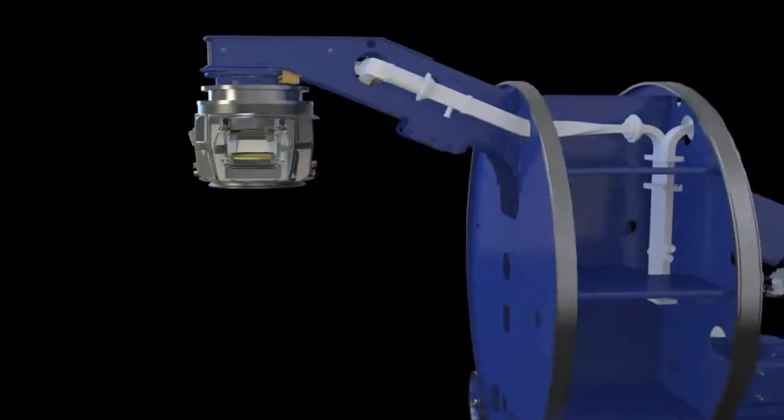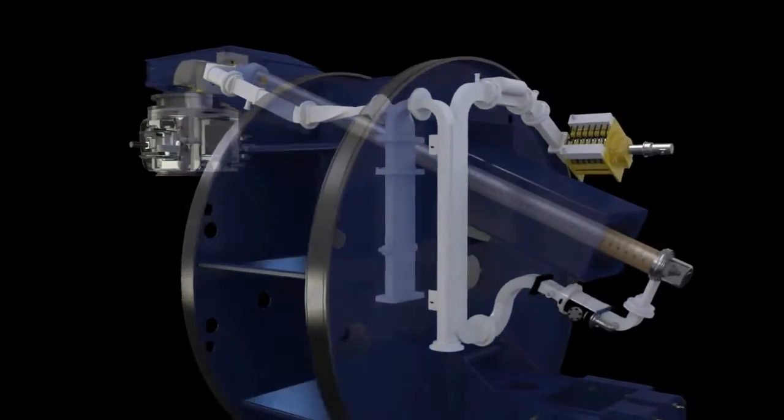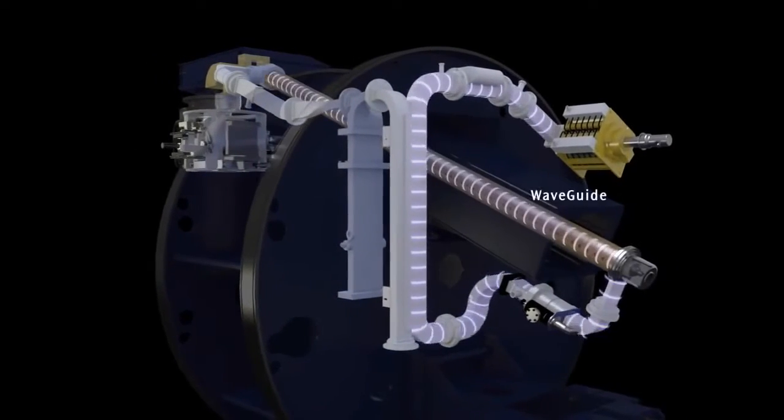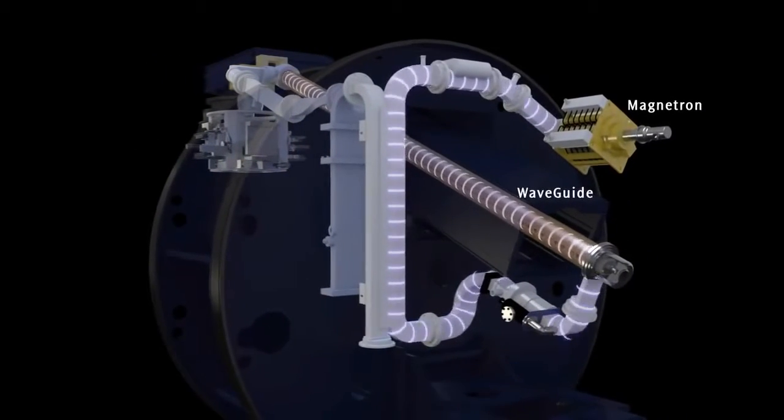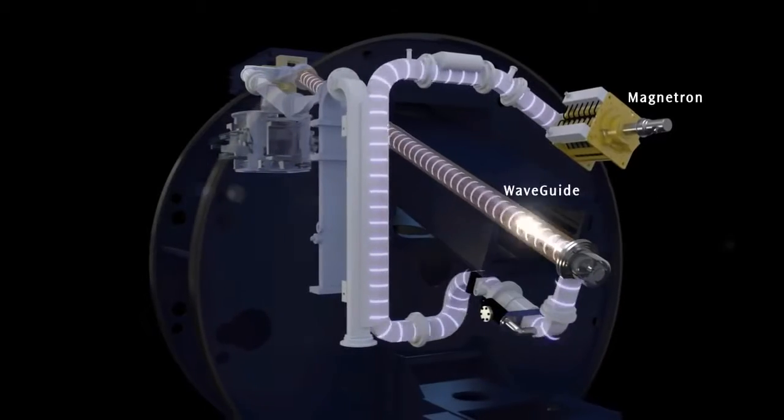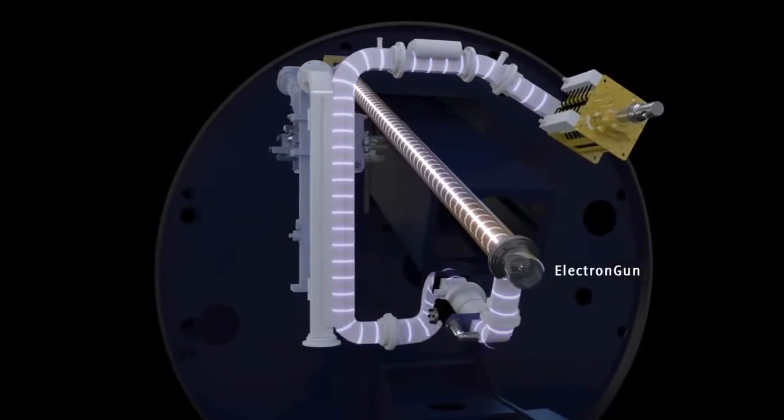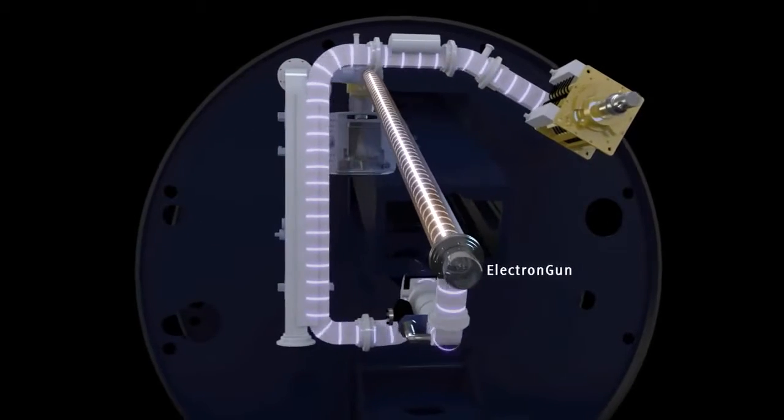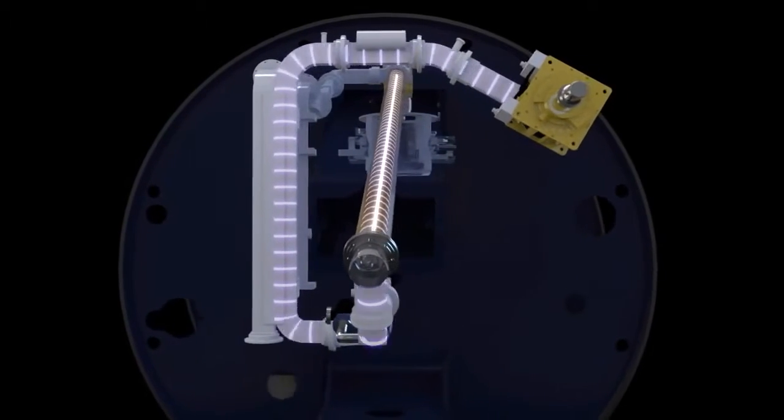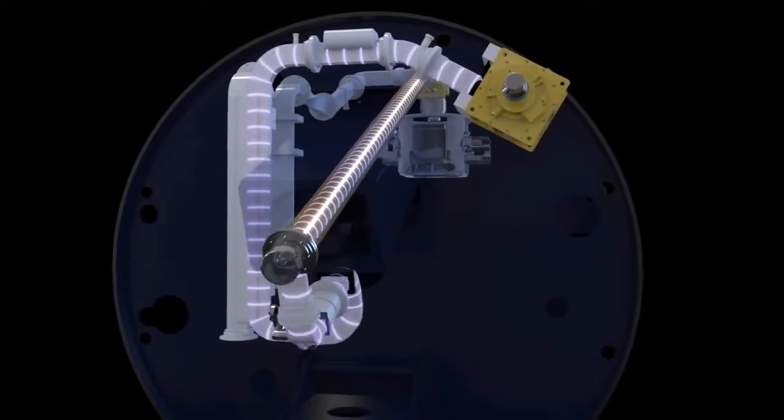Beam generation. Radio frequency waves are pulsed into the waveguide by the magnetron. This is synchronized with the injection of electrons into the waveguide by the electron gun. The radio frequency waves accelerate the electrons along the waveguide to a speed approaching the speed of light.